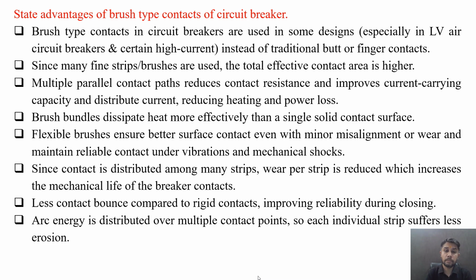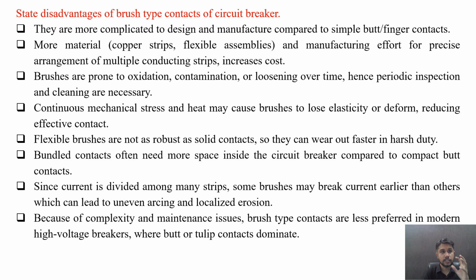Flexible brushes ensure better surface contact even with minor misalignment or wear and tear, and maintain reliable contact under vibrations and mechanical shocks. Since contact area is distributed among many strips, wear per strip is reduced, which increases the mechanical life of the breaker contacts. Less contact bounce compared to rigid contacts improves reliability during the closing operation. Arc energy is distributed over multiple contact points, so each individual strip suffers less erosion or corrosion. So these are some advantages of brush type contacts of circuit breaker.